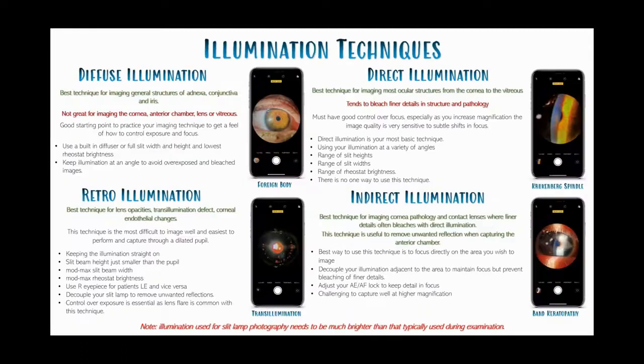For illumination techniques: for general structures of the adnexa, conjunctiva, and iris, use diffuse illumination. It's not ideal for fine details such as the cornea, anterior chamber, lens, or vitreous, but it's a perfect starting point to get used to imaging — ensuring your alignment is right and exposure isn't too bright. If your slit lamp has a built-in diffuser, use it. If not, use a full slit width and height with very low brightness on the illumination arm. Keep the illumination arm at an angle to avoid overexposed or bleached images.